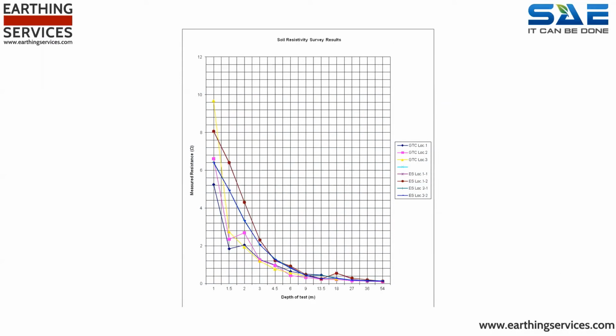This demonstrates the test results plotted on a graph, which shows a commonly observed trait. For a given area, the deeper into the ground you test, the more likely the results will be consistent. This is partially a consequence of a lack of human interference. After all, humans usually do not disrupt ground to depths of 54 meters.